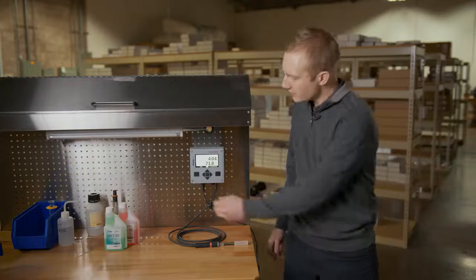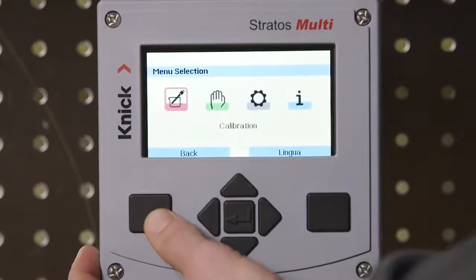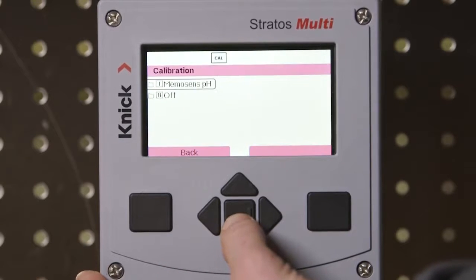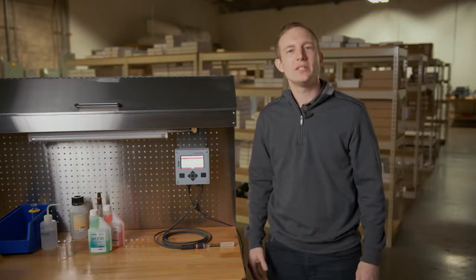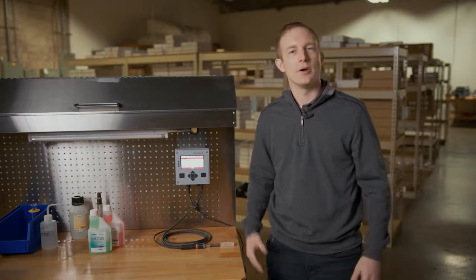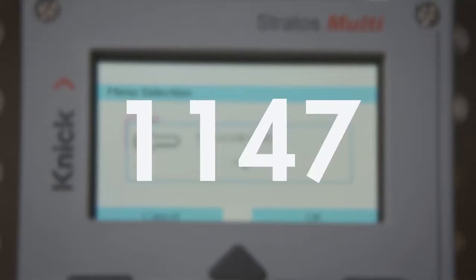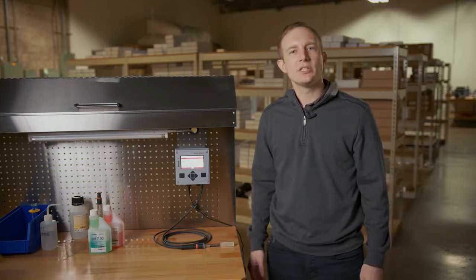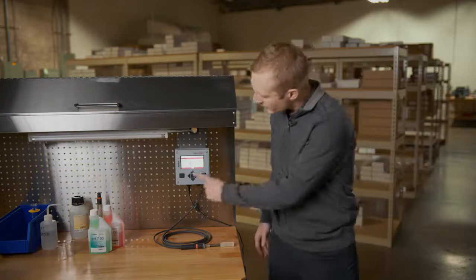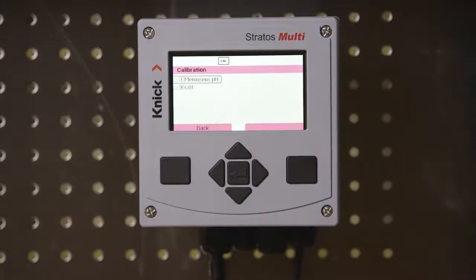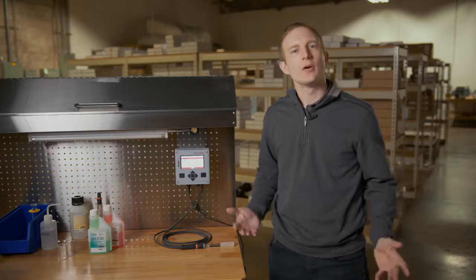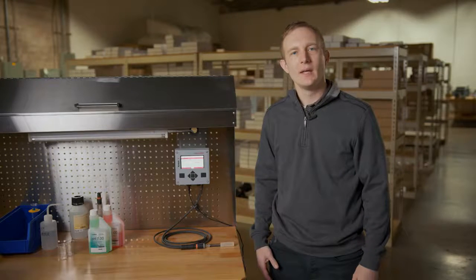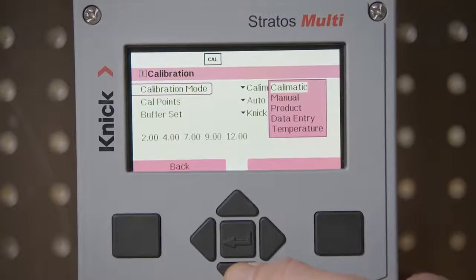Let's begin by pressing Menu on the main screen and then Enter on Calibration. If access to the calibration menu is blocked via a passcode, please note that the default is 1147. Once inside the calibration menu, we will select the Memosens pH sensor that is connected to channel 1 of our transmitter.